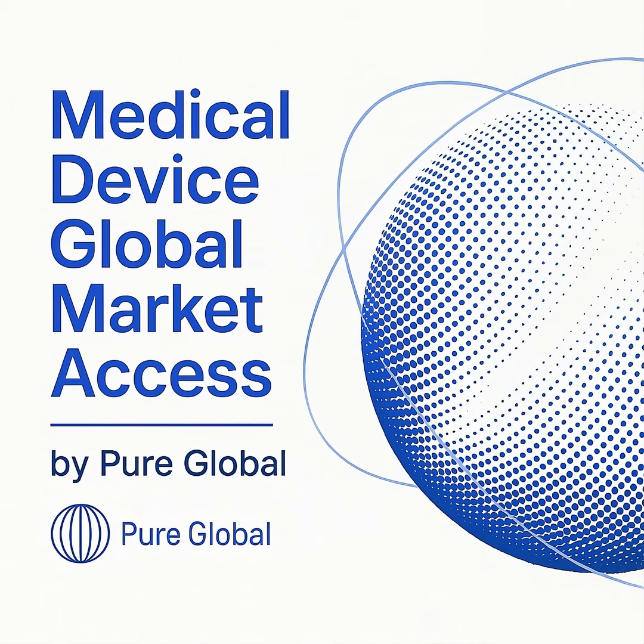Today we are diving into a significant development from the US Food and Drug Administration that impacts the rapidly evolving field of artificial intelligence in medical imaging. On June 17, 2026, the FDA issued a final order establishing a new device classification for radiological machine learning-based quantitative imaging software with a predetermined change control plan. This order classifies the device type into Class 2, subject to special controls, creating a more predictable and streamlined regulatory pathway for manufacturers. This new classification is a pivotal moment for AI and machine learning medical device developers.